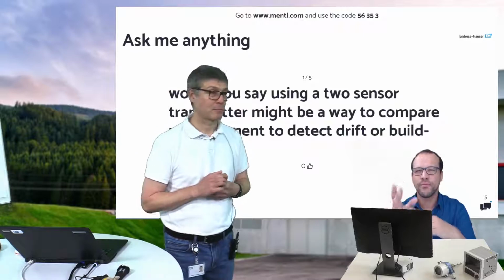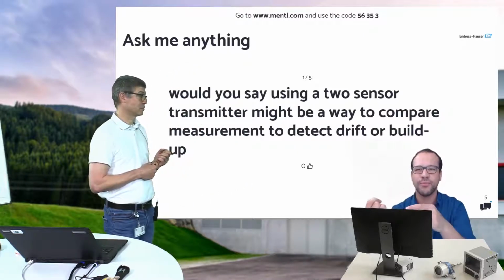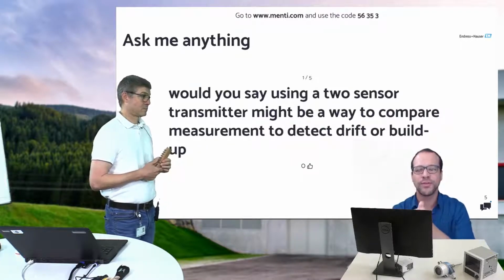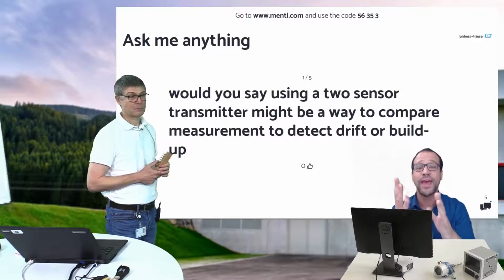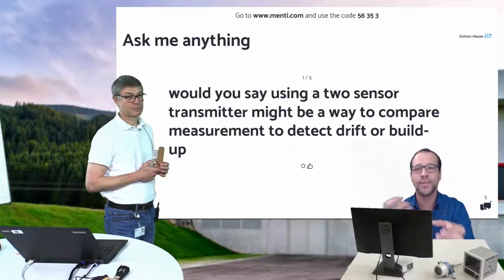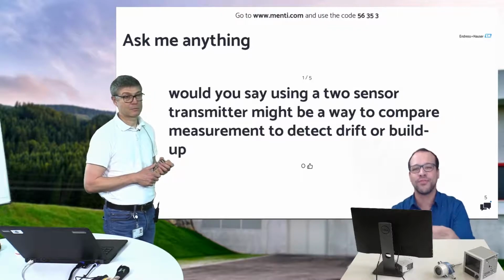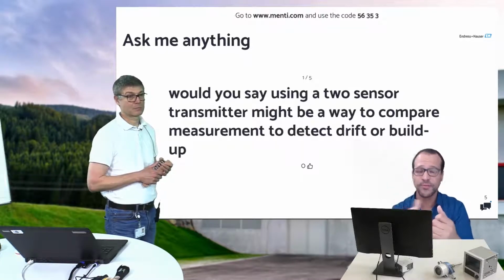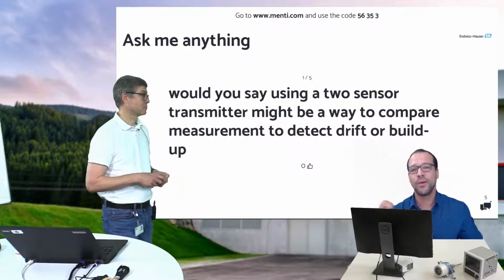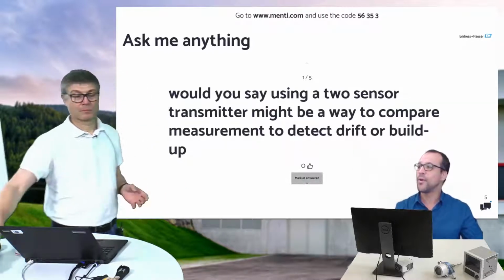Furthermore, please also think about the inaccuracy that an in-the-field calibration brings with it. In a calibration lab, of course, you can reach a higher accuracy. So that would be a better matching. And if you order, for example, a spare sensor together with a sensor transmitter matching, then you get a calibration certificate with those coefficients, and you can put that in the transmitter. And with our Bluetooth transmitters, for example, that's rather simple with a nice smartphone app to manage it.